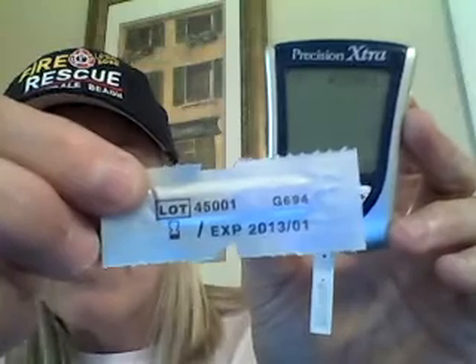You should get the screen to light up. Alright, it had all kinds of different things that lit up. You want to make sure that the screen is working. Okay, so the first thing you're going to do, take your calibration strip. You're going to insert it into the machine to make sure that it knows which calibration is going to be set to which lot number of test strips you're going to use. So right here is set for 45001, test strips 45001. So these are compatible, it has been calibrated.